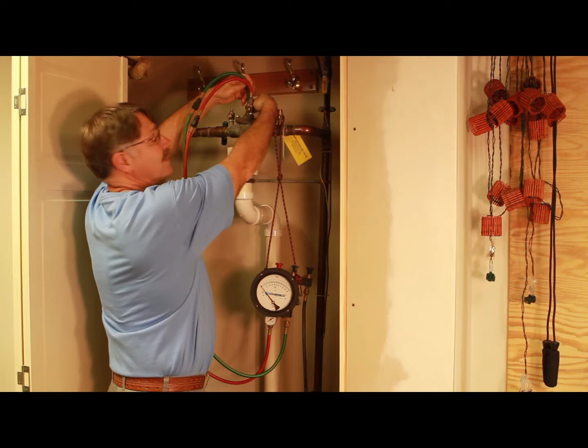And what I test it with is this. I am a certified tester. This is my test kit. So I'm going to test this device. There's these three test cocks up top that I have to use. This device has 3 hoses on it. I have to use all three. In this particular device I have to actually test three things. On the double check I'm only testing that each check works. On this one I have to also test that the relief valve relieves at the proper pressure.